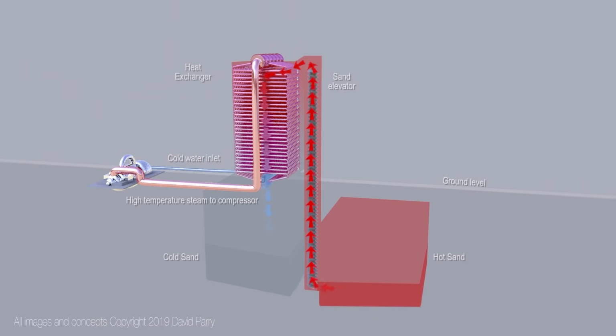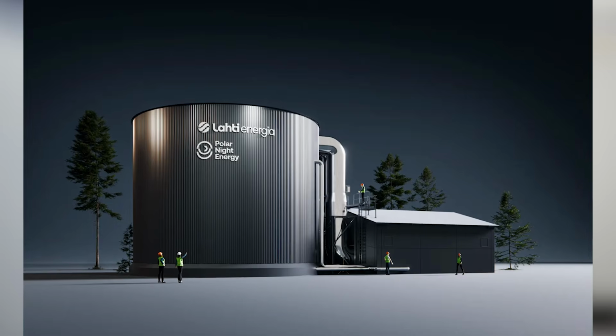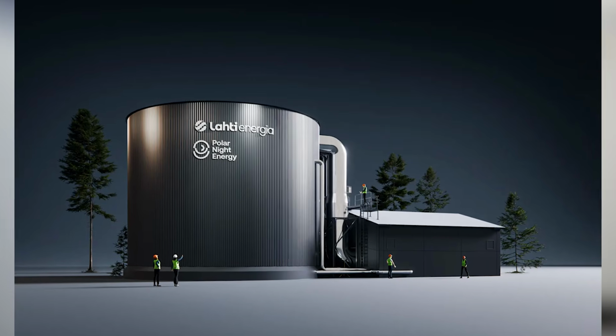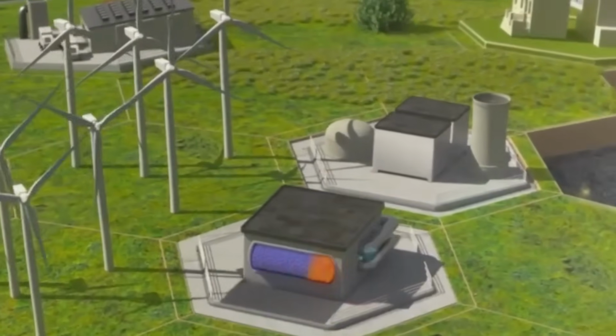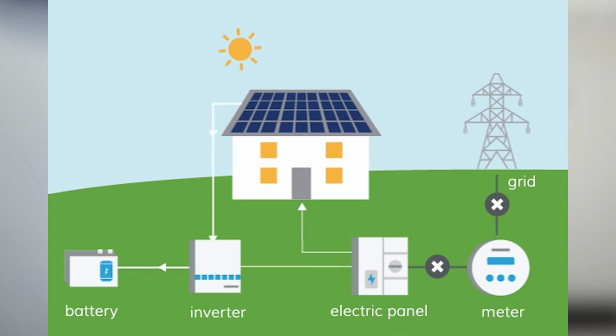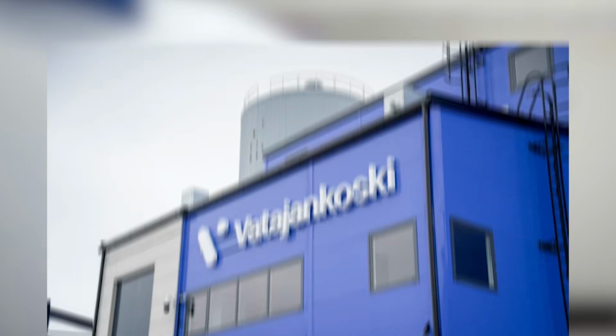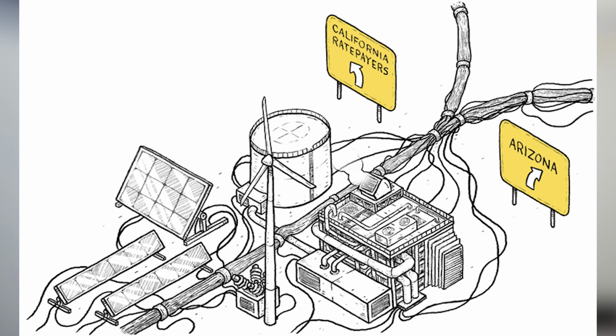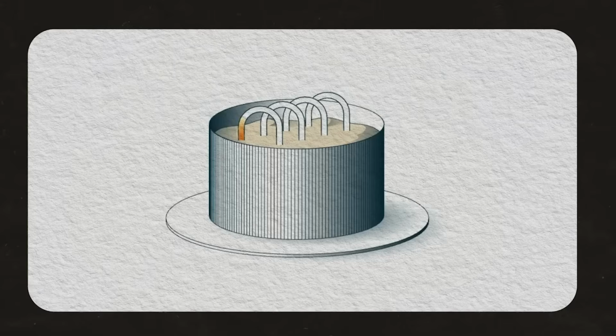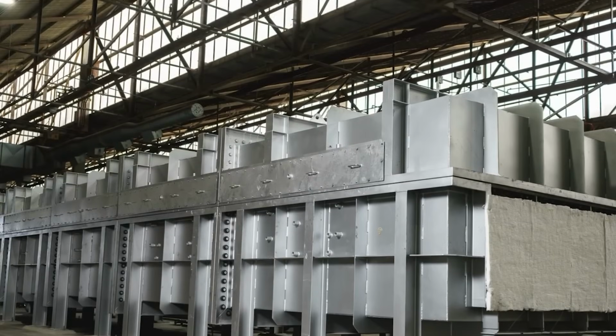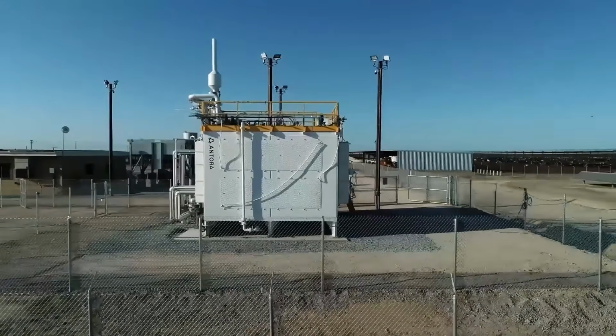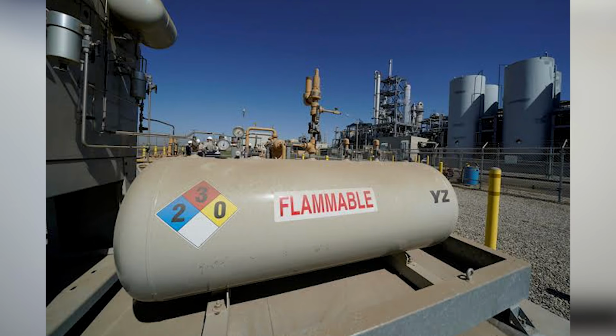The Kankaanpää installation is not a pilot demo tucked behind a university fence. It is a working piece of energy infrastructure. Polar Night Energy's sand battery uses a steel silo approximately 4 meters in diameter, packed with roughly 100 metric tons of standard construction-grade sand. It stores up to 8 megawatt-hours of thermal energy. The local utility, Vatajankoski Oy, charges the sand using surplus wind and solar electricity purchased during periods of oversupply, when spot market prices drop close to zero or even go negative on the Nord Pool exchange. When heating demand spikes in winter, the stored heat feeds into the town's district heating network, directly displacing natural gas combustion.